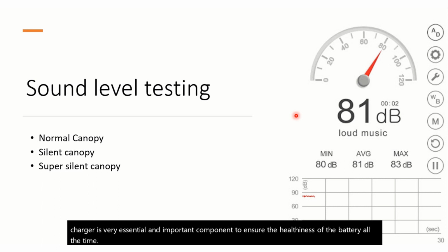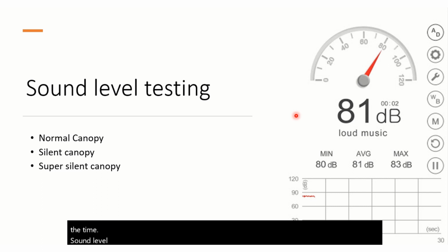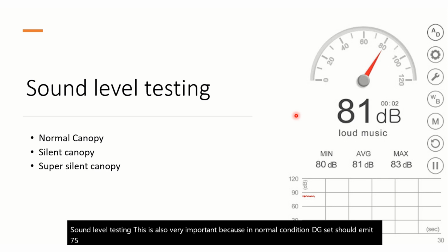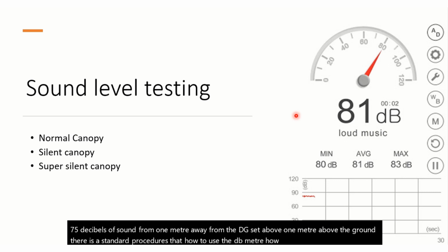Sound level testing. This is also very important, because in normal condition a DG set should emit 75 decibels of sound from 1 meter away from the DG set, 1 meter above the ground. There are standard procedures for how to use the dB meters, how to hold them, and how to take a reading at different angles.